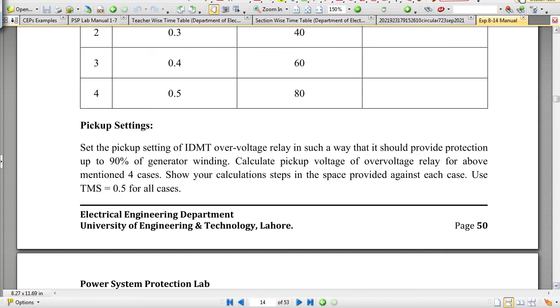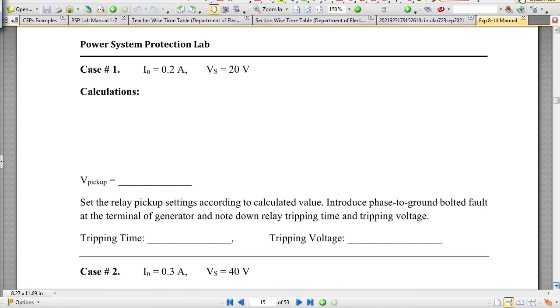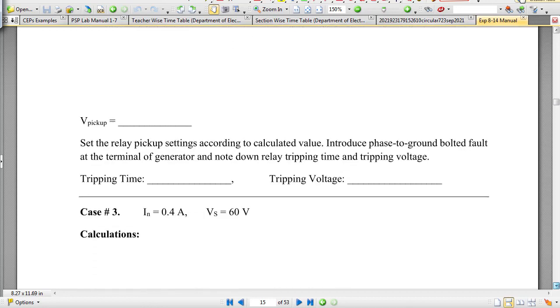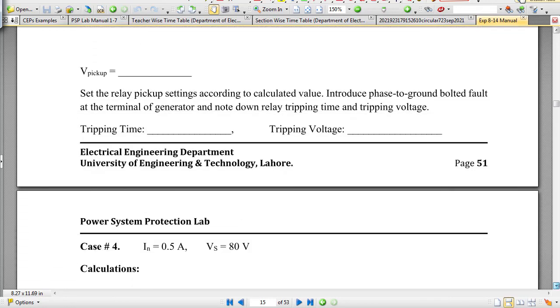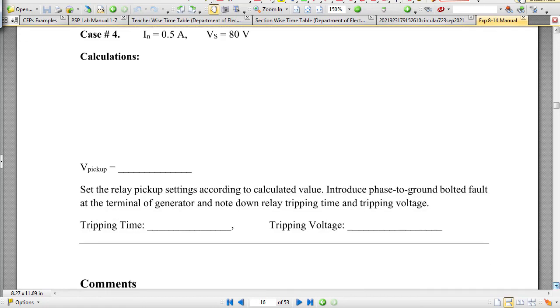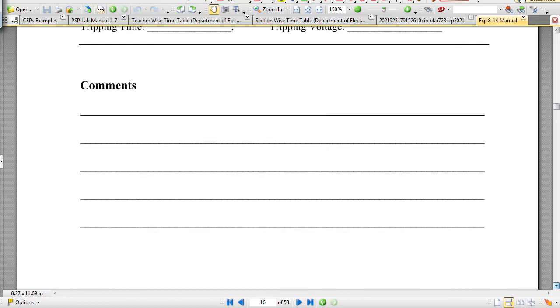After doing this setting, protection of 90% of the winding, the student will have to perform the calculation for the selection of Vpickup, what the value of Vpickup should be for each case. For all these 5 cases for which they have calculated the grounding resistance, they will calculate Vpickup, set that Vpickup in the relay setting, put a fault on generator phase A, and determine the tripping time and tripping voltage of the relay. Then the student will describe their observation in the comment section. Thank you very much.